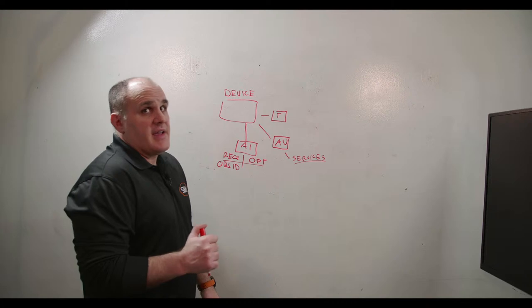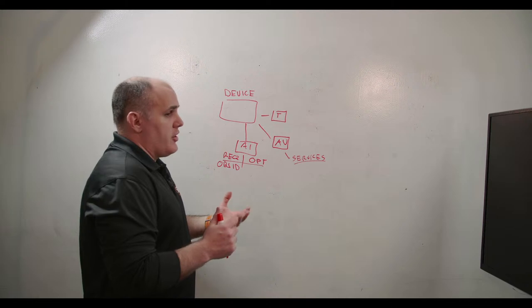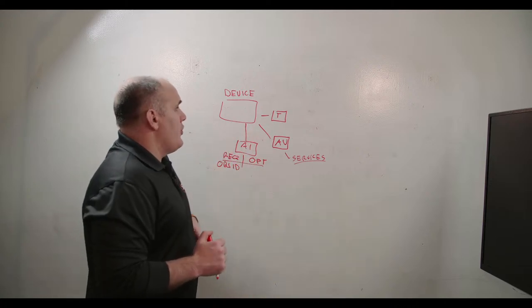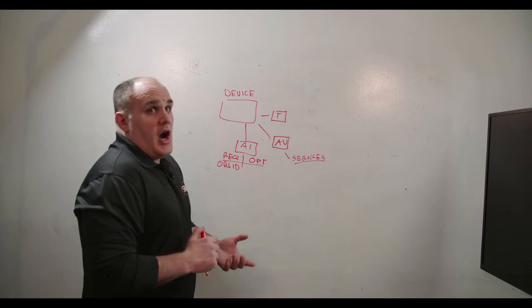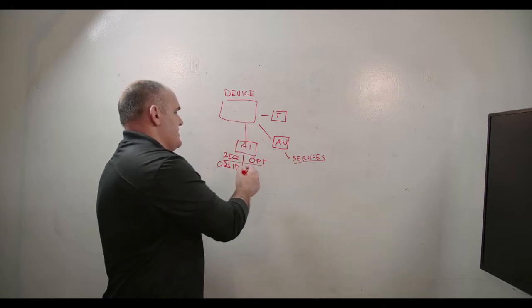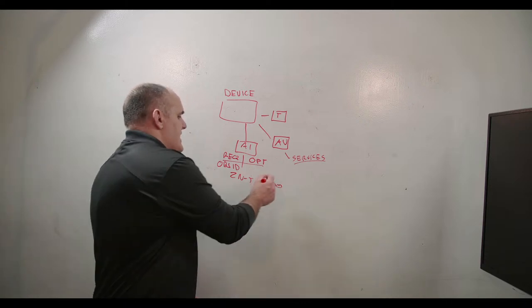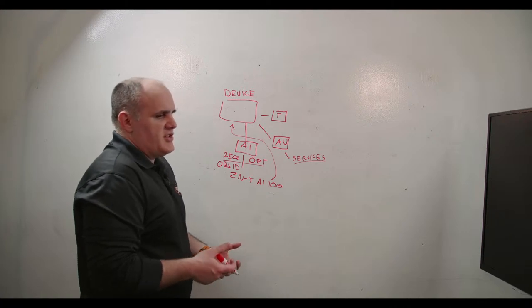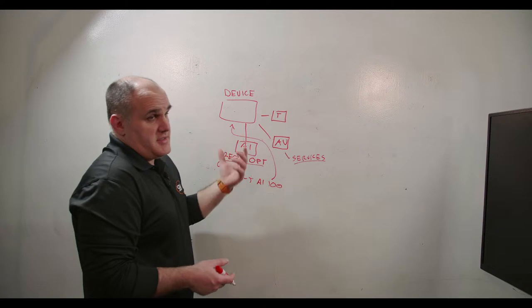I see this all the time with people who are brand new to BACnet: they'll try to map in AI points from a BACnet chiller or air handler and try to command them, but the AI has no priority array. It does not support the write property service, and thus you can try to command it all day long — it's never going to write. The AI is nested under the device, which is why you can have multiple AI 100s across different devices, as long as each is under a unique device ID.